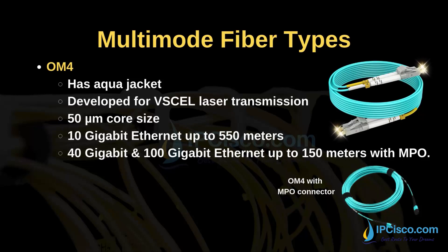OM4 has an aqua jacket too. It is developed for VCSEL laser transmission. Its core size is 50 micrometers. It supports 10 gigabit ethernet up to 550 meters and 40 gigabit and 100 gigabit ethernet up to 150 meters with MPO.